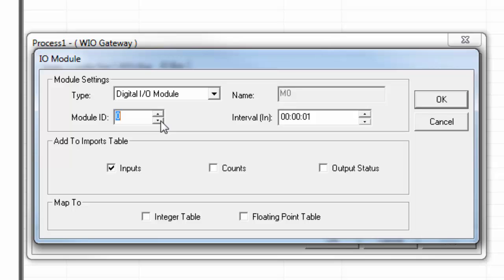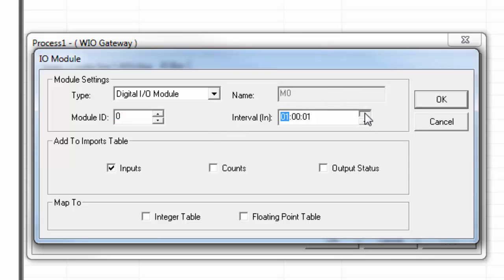Each module in a group must have its own unique ID. Note that the ID dial on the module cannot actually be reset with the power on. So you can't just set it to a different ID on the fly. And this is because the ID is only read by the gateway once on startup. So if you need to set the dial on an IO module to a different ID, you would have to power down the group, set the dial and then power back on.